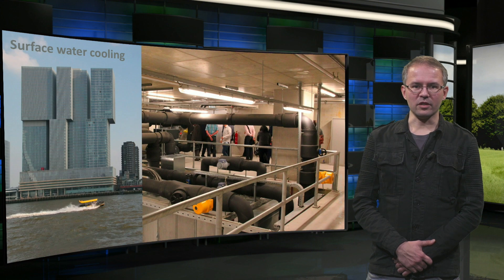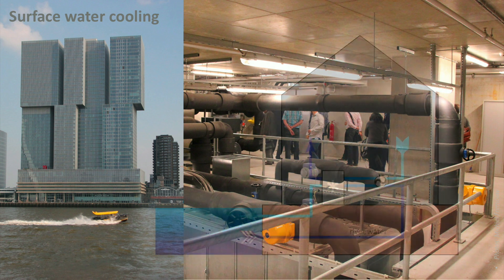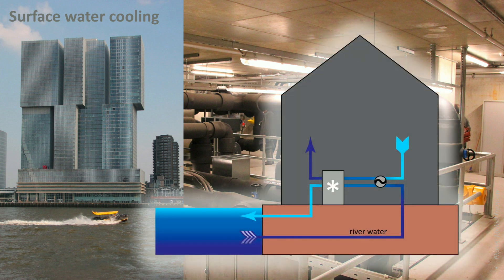The second source I will be showing is surface water. Lakes, rivers and the sea can all be used for heating or cooling. An example that combines several technologies is the Rotterdam building, which uses the Maas river for cooling. Here, river water is pumped through the cooling plant in the building and either used with just a heat exchanger, or if needed, cooled down further with a heat pump. The same principle can be used for heating — for example with seawater, which is relatively warm in winter — however, a heat pump is then necessary.